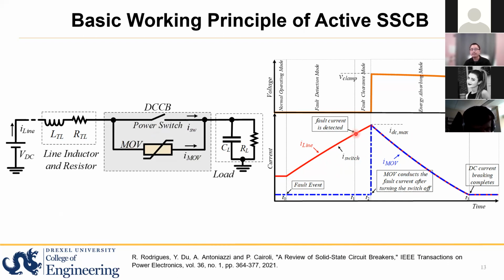After we detect this, we ask the solid state switch to turn off. When this turns off, we can see it will generate a reverse current, or a huge current, on the switch. Since we have this MOV, it is used to absorb the energy and limit the peak current and peak voltage. Then you could see we have a peak voltage here, a kind of flat waveform.